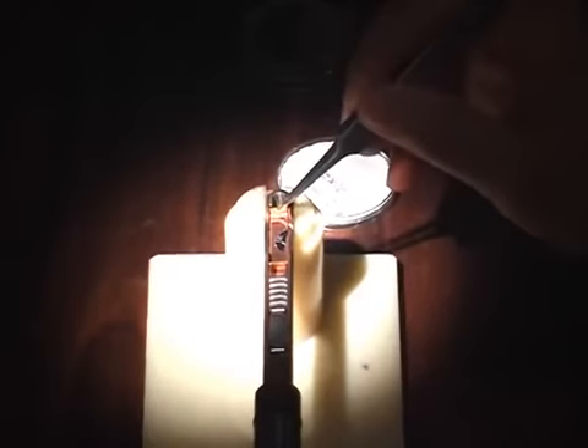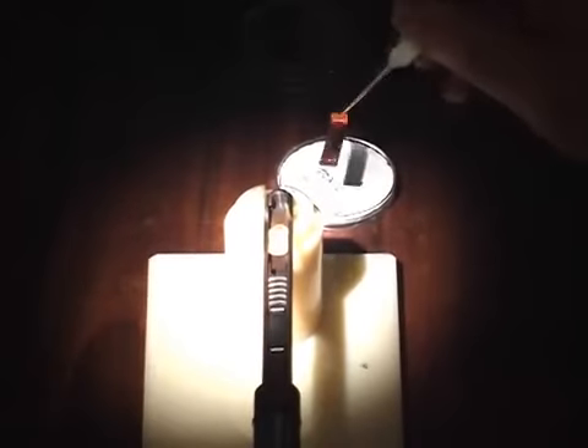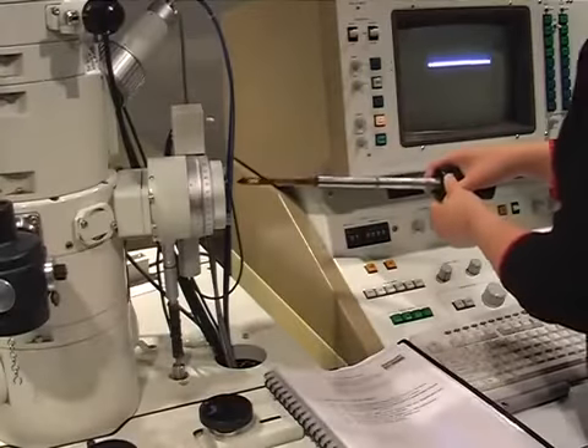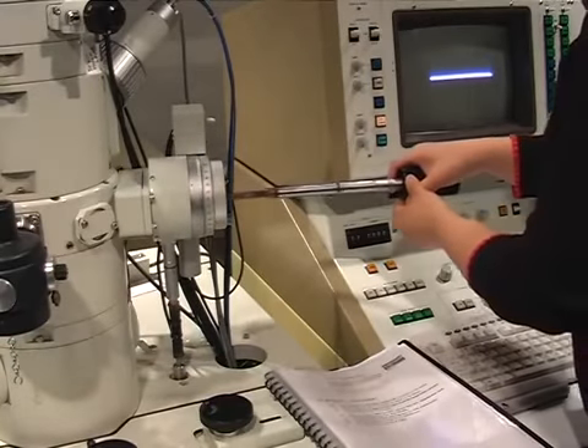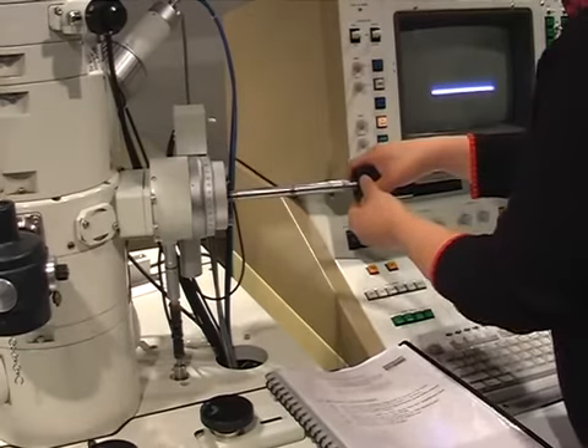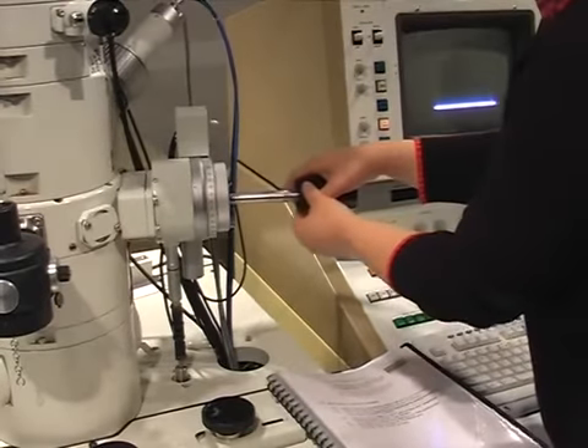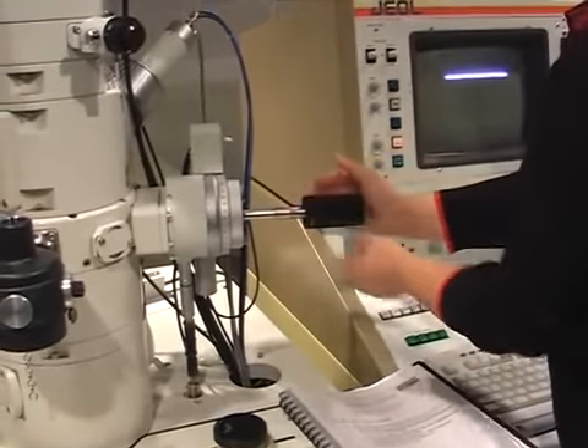Using metal forceps, drag the serrated metal clasp towards the O-ring side of the sample holder. You will hear a click. Use fine forceps to remove the specimen stub. Carefully slide the sample holder into the goniometer until the sample holder comes to a stop. The key should have just gone into the keyway and no longer be visible. Push the sample holder in about 2 millimeters.